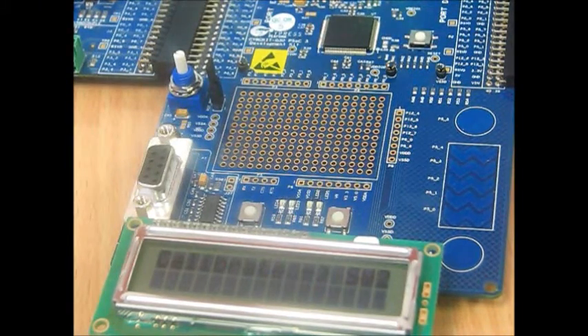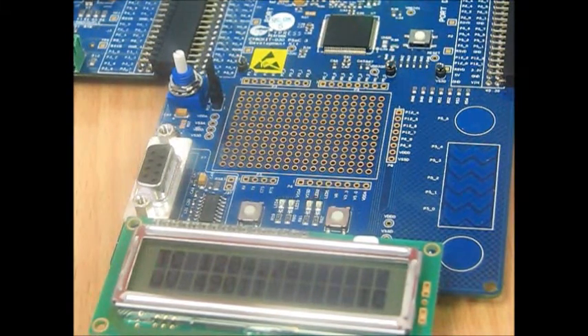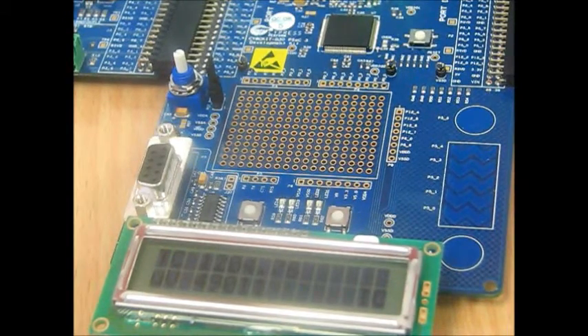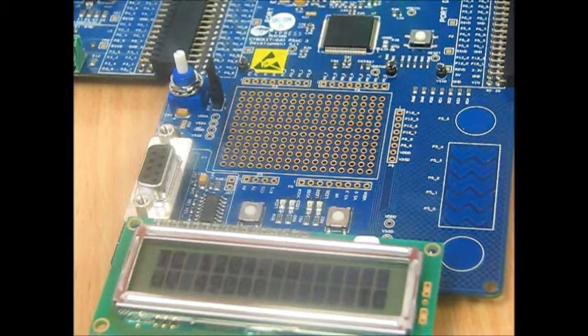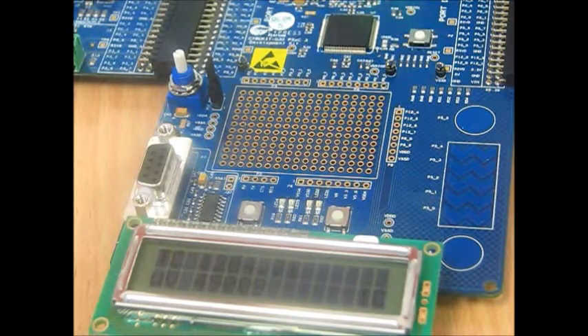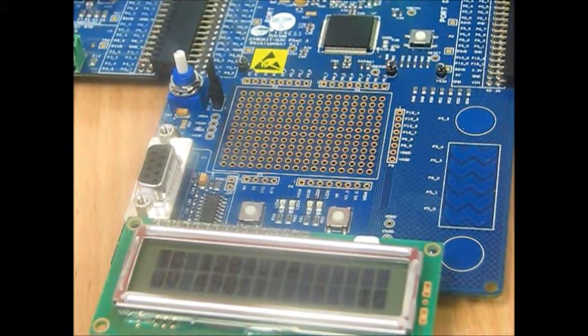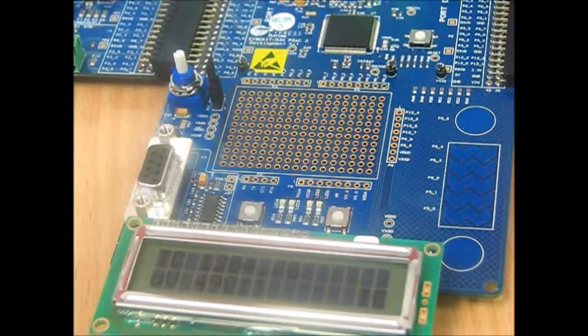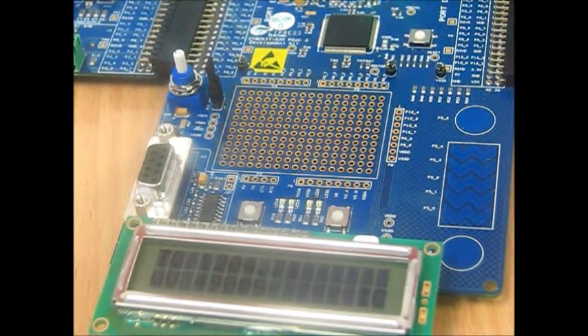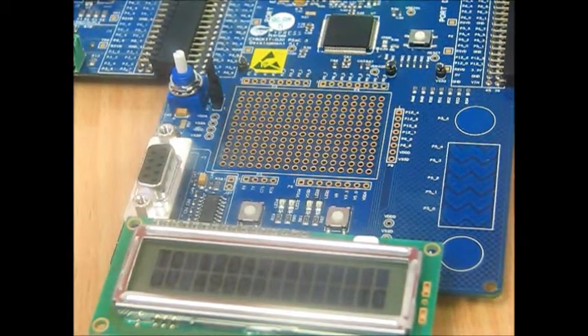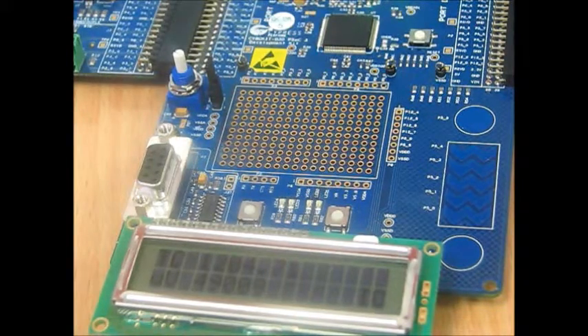After pressing reset, the menu shows clear indications on the directions for calibration. If you do not press switch 2 within 3 seconds of pressing reset, the device doesn't calibrate and directly shows the uncalibrated reading. The uncalibrated reading in this case is 49.010 millivolts. That is actually the reading in the second row.